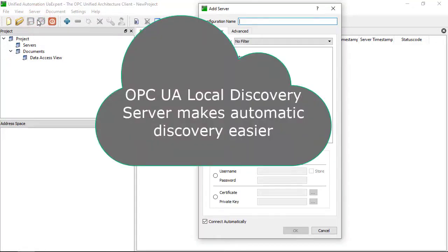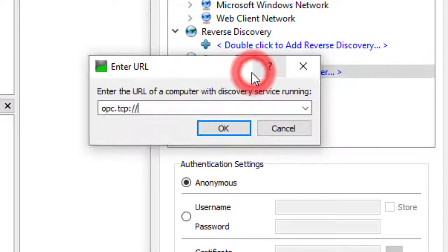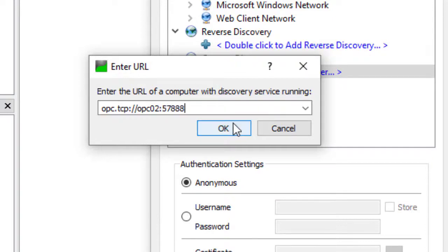If you already have a local discovery server running, you can probably find OPC Expert automatically, but you can enter it manually by typing opc.tcp://OPC02:57888. Capitalization does not matter.